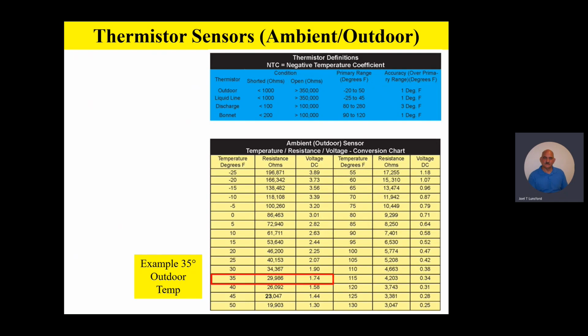Now, team, one other thing that we want to be very, very careful of is that when we're doing any of these sensor readings, we take a good accurate temperature. We have a good quality temperature probe. We take a good accurate temperature of the temperature that that sensor is subject to. So it goes without saying, please do not hold the sensor in your hand. Don't touch the sensor bulb itself, because the temperature of your hand will actually throw that sensor off. So be sure that you don't touch the sensing bulb itself, but if you're going to handle the sensor, just make sure you unplug it at the little harness that plugs off and onto the board itself.